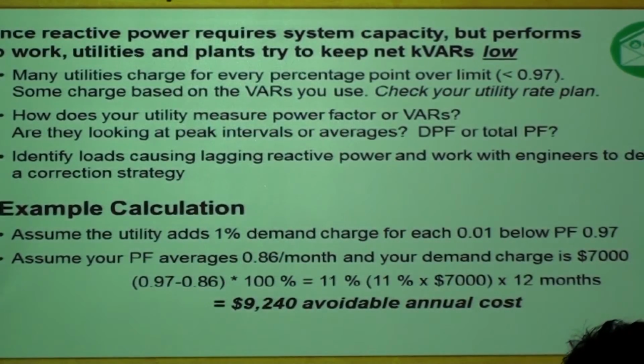Power factor penalties, again, just to show you what it is: reactive power is wasted power. It does no useful work for us, so we want to make sure that you keep that reactive power very low, because it's wasted power. It does no useful work. Many utilities charge for every percentage point over the limit. So every 0.01 you go below 0.97, they will charge. Of course, again, check your utility rate plan. Now, I can't confirm, but I know in Saudi they do this. They do have a standard there. How does your utility measure power factor?